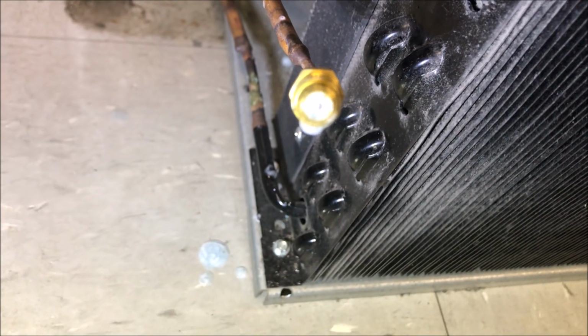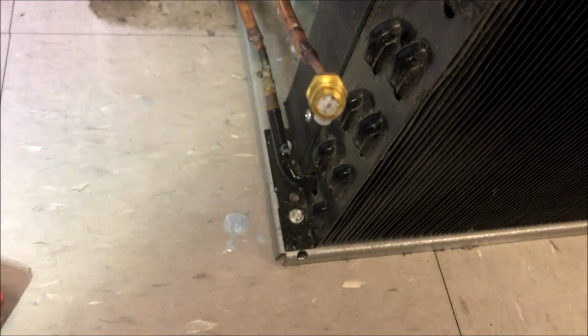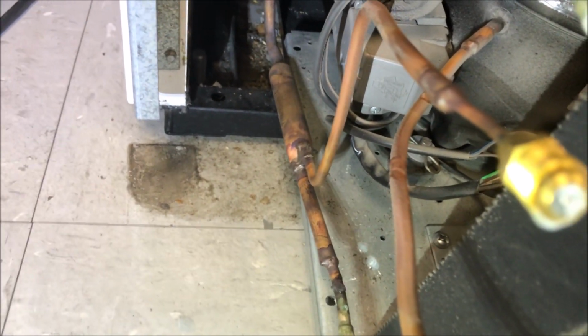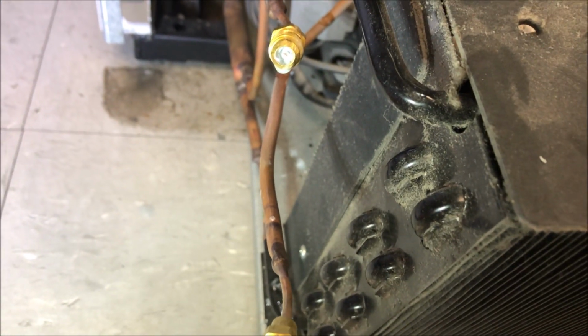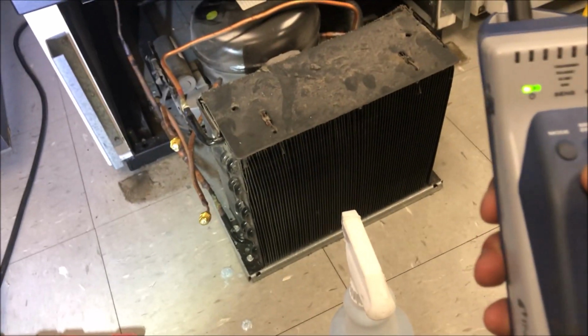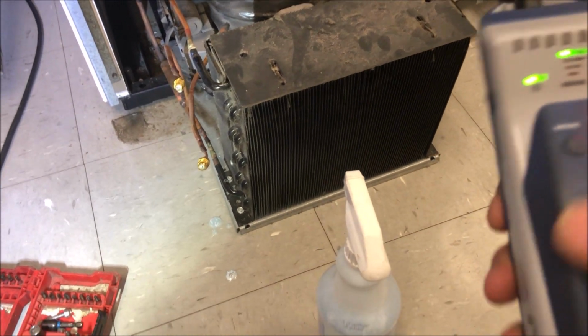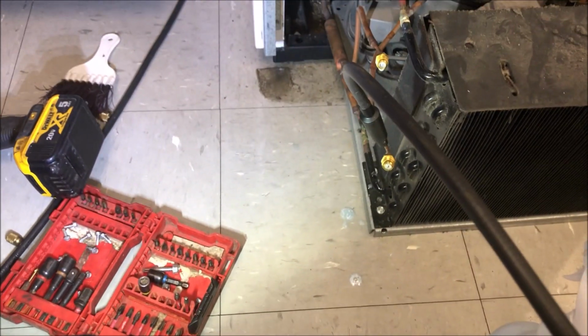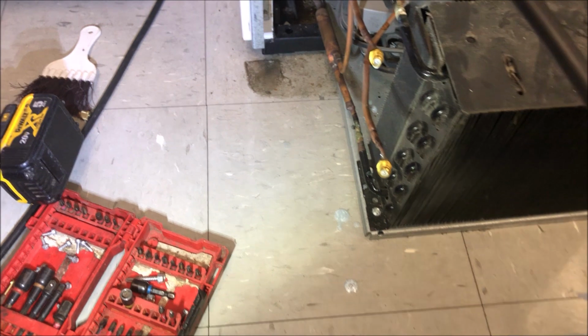leak test the condensing unit. I'm going to soap up the Schraders because I find I always get false readings if I just hit that with the leak detector. And then we're going to hit up all the joints that the previous tech has brazed and all the factory joints. Let's make sure we don't have any leaks in this bottom section here. We're going to use the mode where I look for the general area of the leak. So I just changed the setting there.